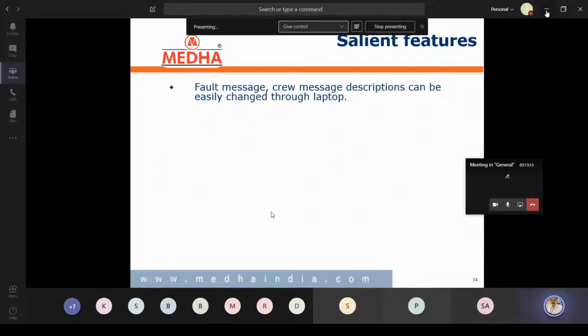Next, fault message and crew message descriptions can be easily changed through a laptop. Earlier, if you wanted to change any display message as per the customer, we had to change the hardware. There was a hardware IC that we had to change. But now with the display configuration software, as per the end user requirement, any message can be changed simply by using a laptop. But we require an authentication letter, so that individual schedule-wise changes can be made.